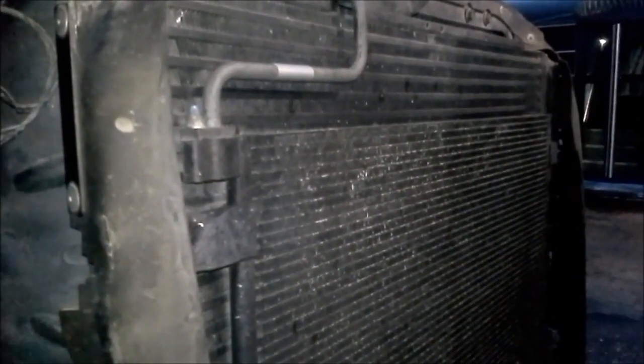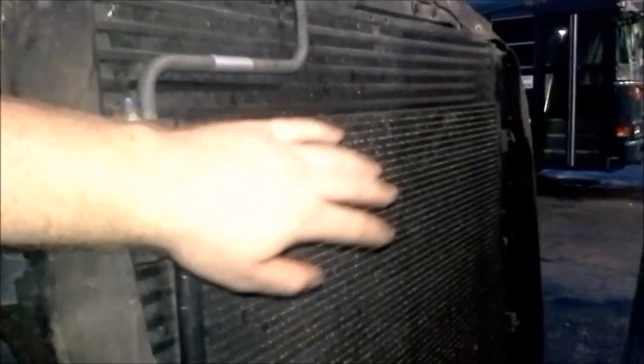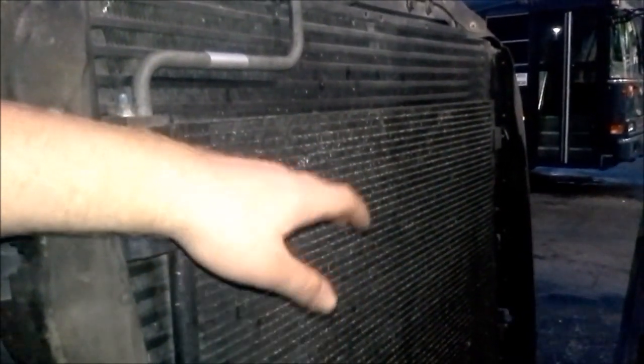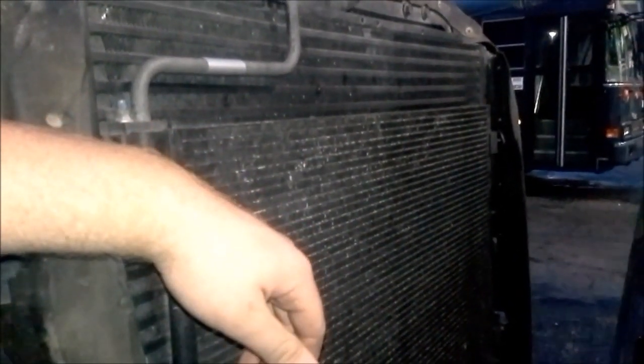The condenser is up at the front here. This bad boy tends to be blocked out with a bunch of bugs, rocks. Yeah, I've seen it, some concrete trucks get a little bit of concrete, that sediment in there, and then they get some water, get a bad rainstorm, it tends to turn this thing into a block of concrete. Therefore you got to replace the whole condensing unit. But this right here is what contains the gases on this side of the HVAC system.